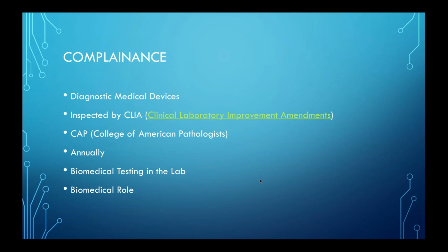We have diagnostic medical devices. So when we're looking at the equipment, if you're going to risk rank medical equipment, the laboratory falls under diagnostic, and that's usually a 3 on the level. It's right in the middle of the urgency. They usually get PM'd once a year.